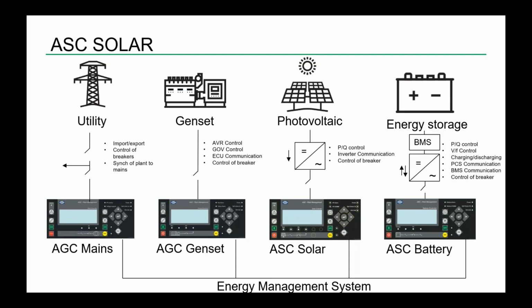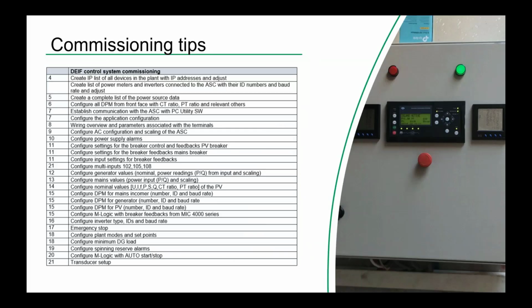When you do commissioning, you have to follow some steps. We have made a commissioning manual. It's a good idea to look at this, because there we have some chapters where we go through what you need to do. You can see it starts pretty basic. Create an IP list of all devices, create a list of power meters, ID number, baud rate, settings, other things like power source data. So the fundamentals that you need to know. And then you can work your way through the commissioning manual. Usually it works pretty well. This is a generic manual, so it covers both the advanced and the professional solution, and there are some deviations there, but it will take you a large step of the way.